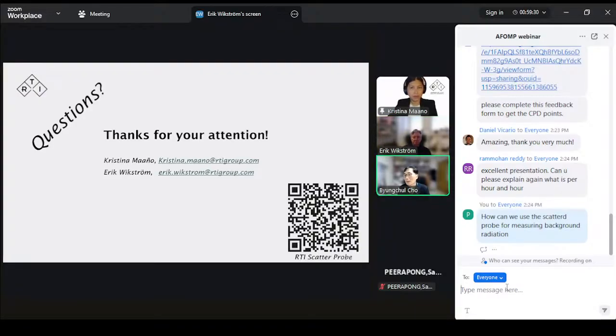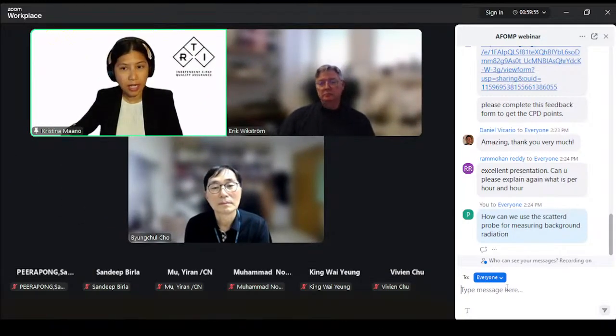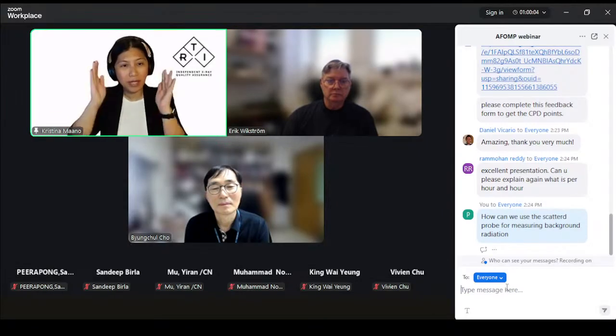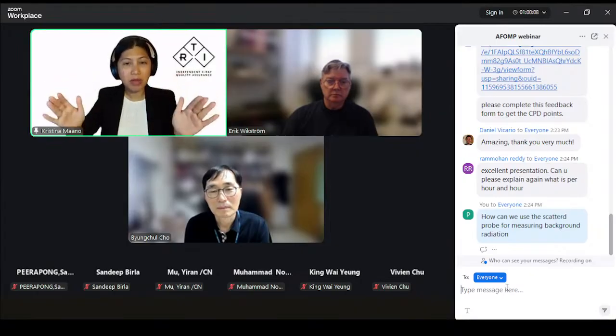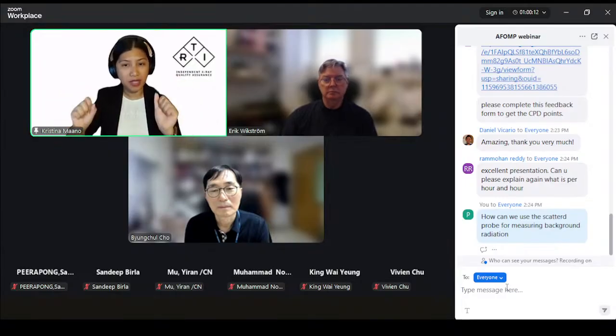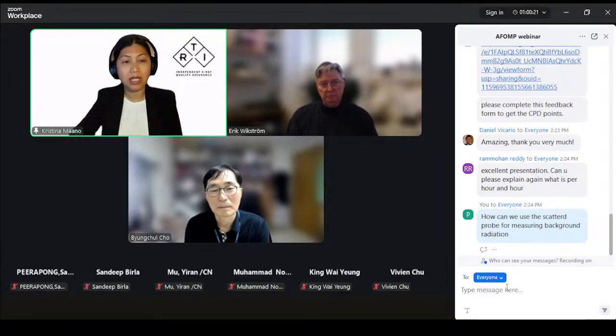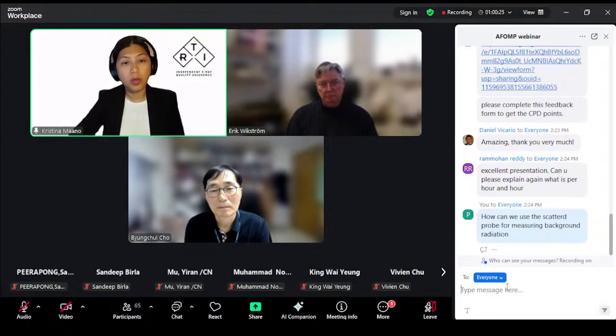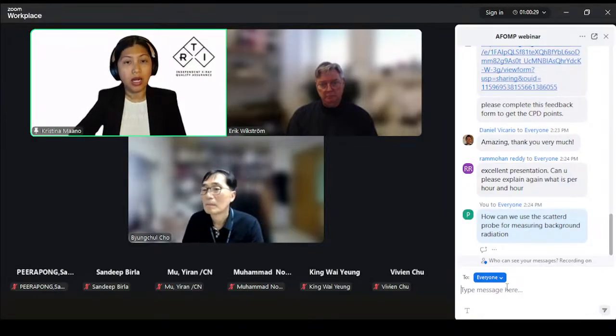Thank you. There is one question. Christina, you explained that in 1 hour and per hour are different concepts, so there is a question about that. We would like to emphasize that when we're doing the calculations for leakage, what we account for is not per hour, but in 1 hour, because in 1 hour it represents the maximum cumulative dose that an area might receive from radiation that escapes the tube housing, even when the tube is not actively producing an image.